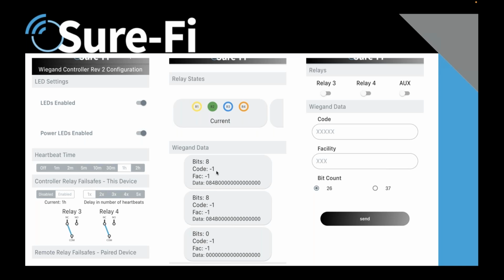If you're doing a 26-bit format, it'll display the code here - the 5-digit code, the 3-digit facility code, and the last 3 bits of Wiegand data. Up here it shows an open or closed circle when the relays change state, and you can swipe left and right to see a history of the relay changing state.